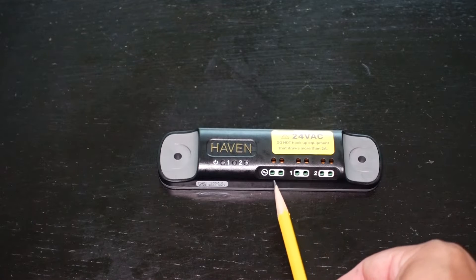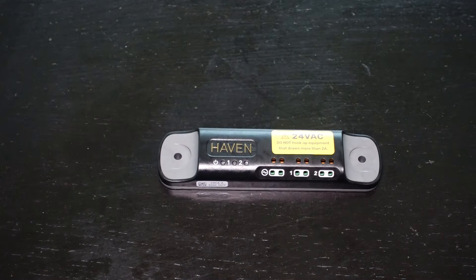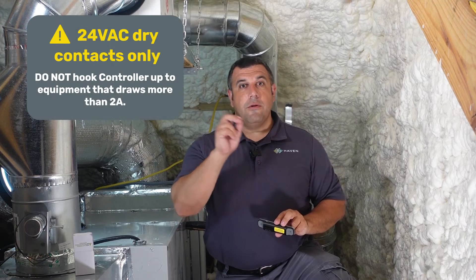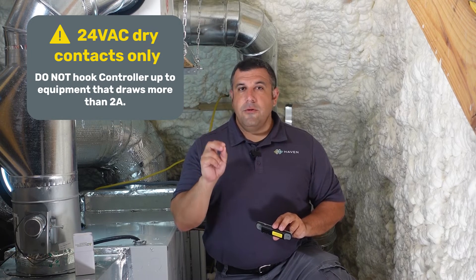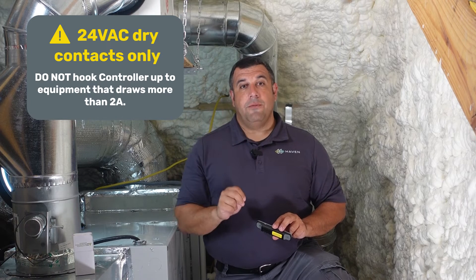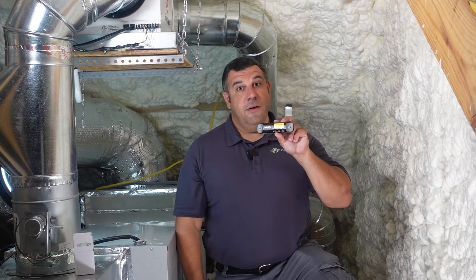Let's talk about power. The leftmost terminals on the controller are for power. Connect these to the R and C terminals from the air handler control board or other transformer that you want to use, as long as it's between 9 and 30 volts AC or DC. The Haven controller is only designed to switch loads under 30 volts with 2 amp max current draw. Do not use the dry contact outputs to switch 120 volt loads or anything drawing more than 2 amps, as doing so could cause damage to both the controller and the HVAC equipment.